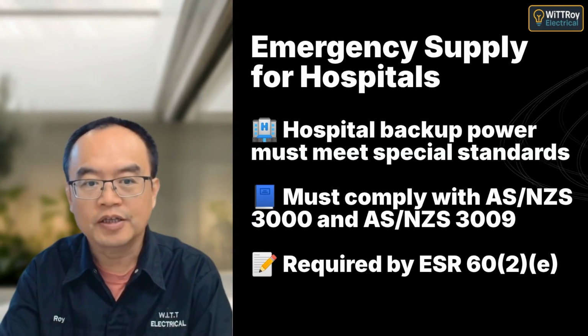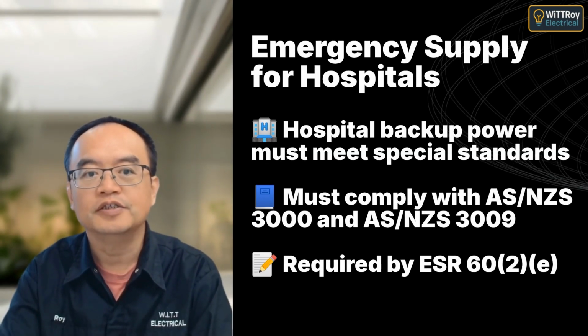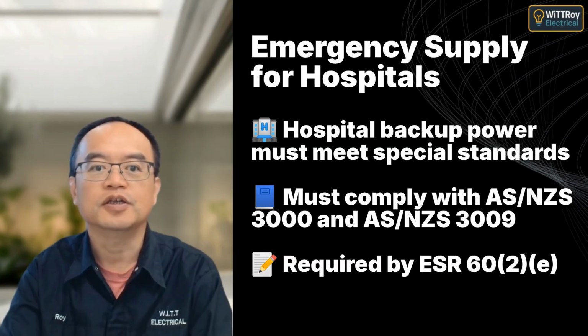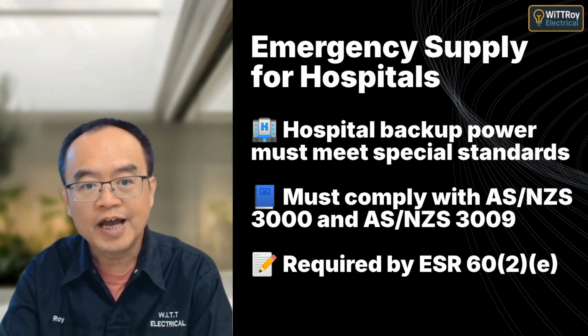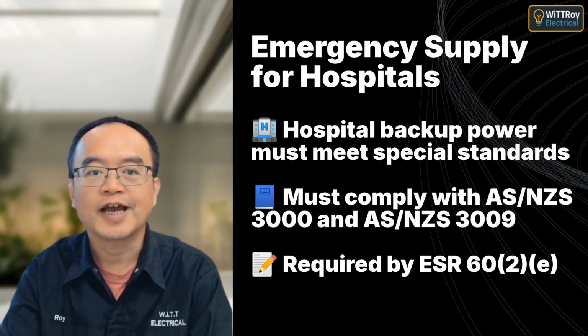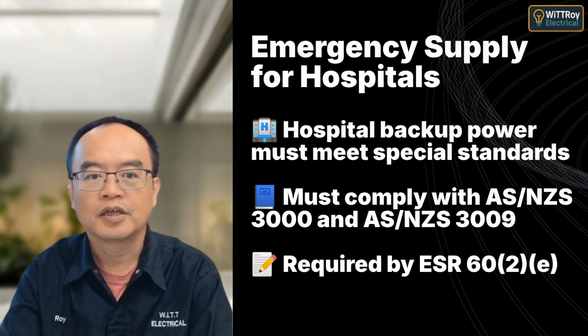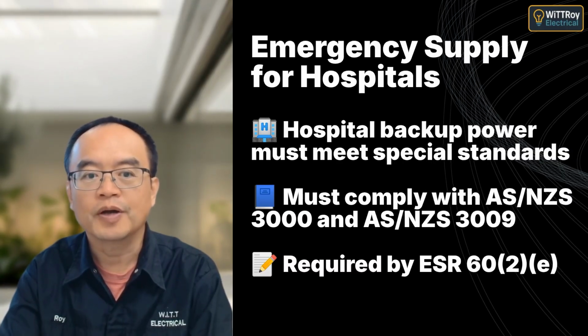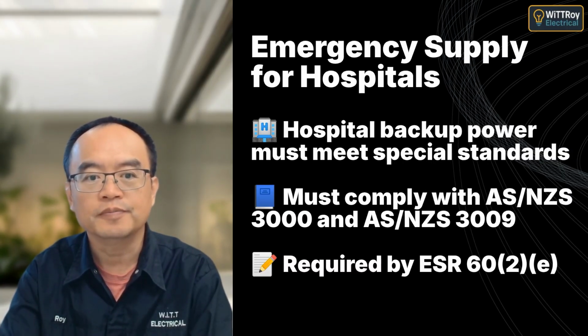When backup power is installed in a hospital, ESR 60(2)(e) requires that the emergency supply system complies with AS/NZS 3000 and AS/NZS 3009. These ensure life-saving equipment remains powered even during a fault or outage.